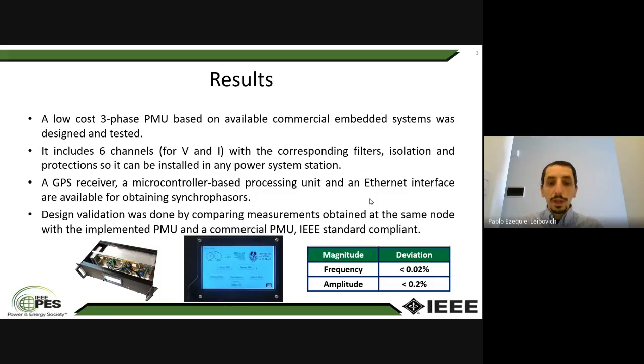To validate the design, and due to the unavailability of a signal generator with the corresponding precision for PMU tests, the measurements obtained in the same node were compared between the implemented PMU and a commercial PMU compatible with the IEEE standards. We can see in the images some photos of the PMU and its graphic user interface. The deviation of the measurements within the compared PMUs was very satisfactory. More details about the design and tests can be found in the paper.